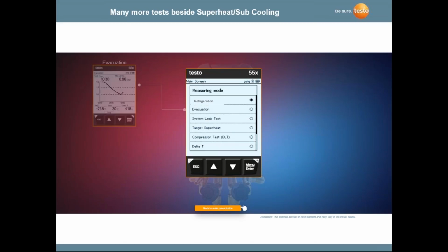You select the different measurements. If you want to do an evacuation test, you go and you select evacuation. You turn on the probe, the vacuum probe. You set the vacuum probe closer to the system through the tee into the vacuum pump, and now you're going to get a micron reading. And I know this slide shows bar, but this is coming from our German headquarters, and they use metric measurements. But obviously, when you select the English language, everything would be in microns, degrees F, and PSI. But this would be just a vacuum micron sensor measurement, a vacuum measurement on the system.